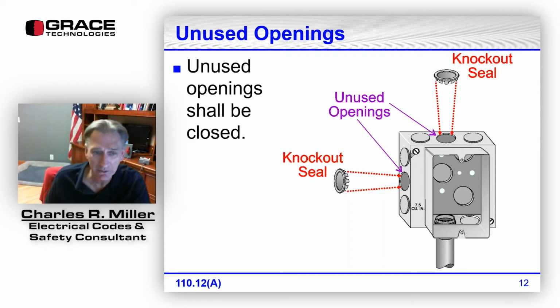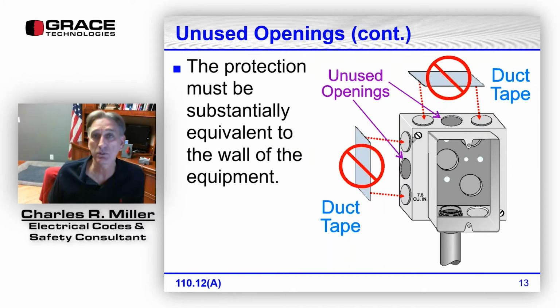So here, we've got a four-square box and a mud ring or plaster ring. For some reason, a couple of the knockouts were knocked out, so we're using knockout seals to close the unused openings. Well, how does it have to be closed? The code book says the protection must be substantially equivalent to the wall of the equipment. So using one piece of duct tape on the outside is not substantially equivalent to the wall of the equipment.